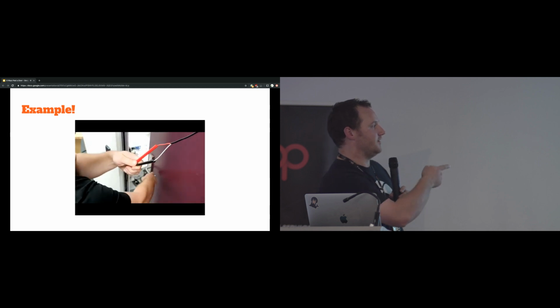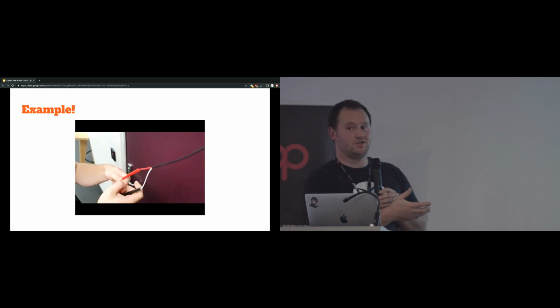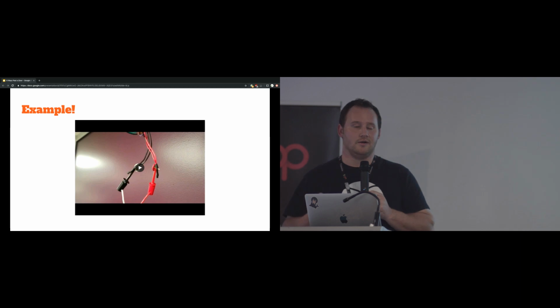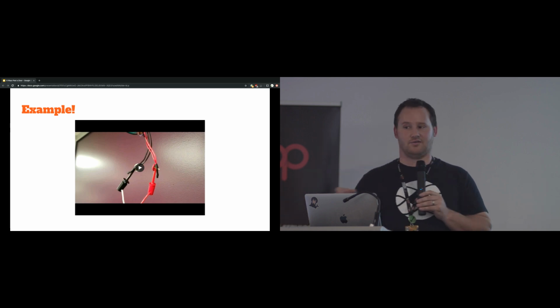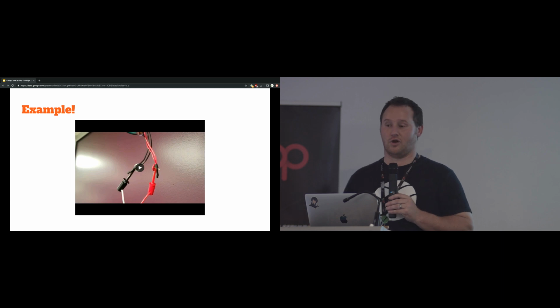So you'll note the card reader stays red, but the door has actually unlatched. The solenoid's been triggered, and the door is able to be opened. Now, noteworthy here, I don't have sound unfortunately, but basically the door access control system was like, something is drastically wrong. I haven't had a request to exit, I haven't had a valid card, anything like that, but the solenoid's been powered and that door's come unlatched and then now the door's opened.